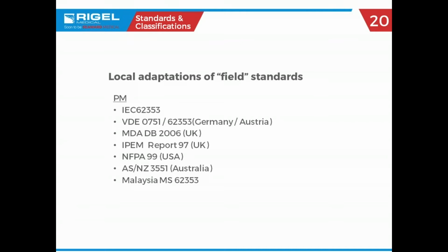So these other standards are just variations of the theme, but they're, again, a little kinder, easier. So the biggest one here is 62353, which is a reduced test set, if you will, of 60601. If you have products coming in from Europe, you look in the service manuals, they will often talk about 62353 testing. That's the field test that they want you to do. Those who do any dialysis machines, they love the 62353 test standard because there's a couple of ways you can do that test, which are easier and safer for you as the biomed to do it. And we'll talk about those. And then, of course, bada boom, NFPA 99.